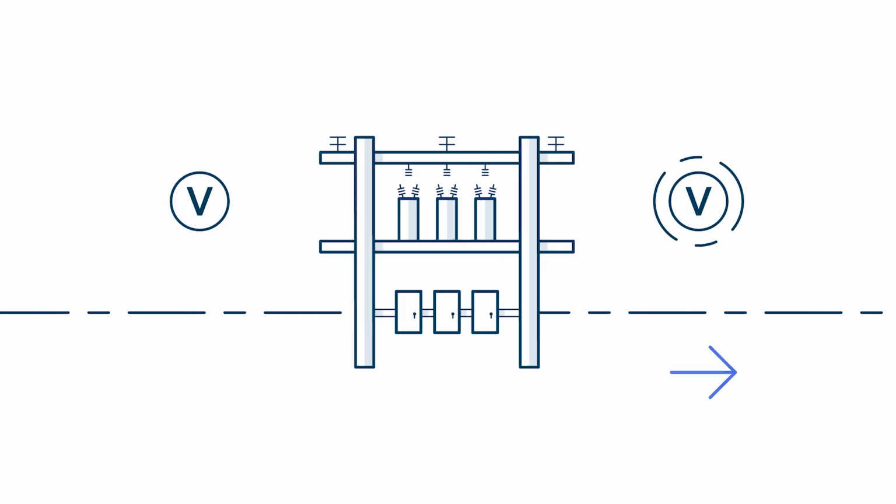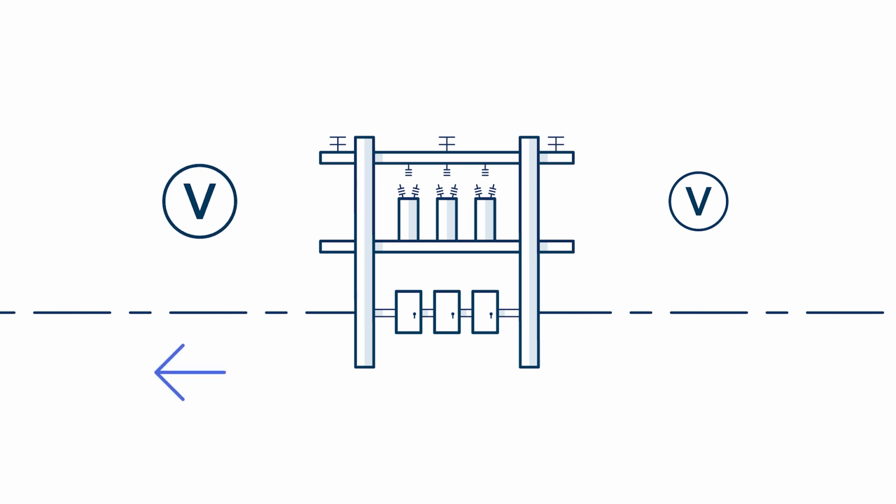We start in the usual way, regulating voltage downstream from the stiff source by default. Meanwhile, the Flex DG algorithm measures the effectiveness of every tap. If voltage doesn't change as expected, the control switches regulation direction and evaluates the effectiveness of subsequent taps.